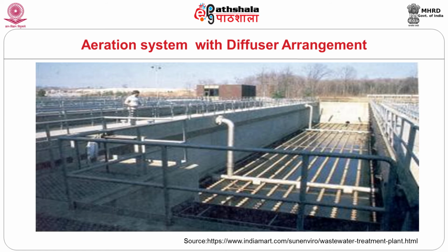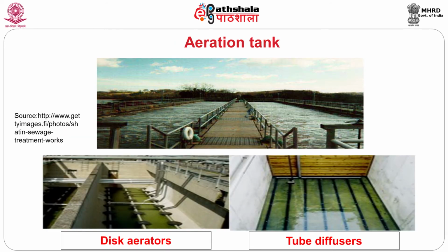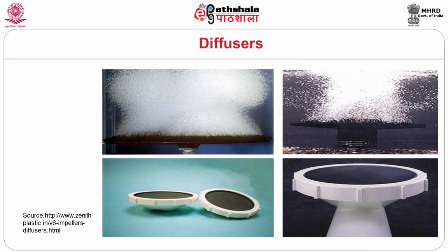So, we have to clean the diffuser plates quite often, otherwise a thin biological film will form around the surface of the porous media. So, this is the diffuser plates at the time of cleaning operation. This is the aeration mechanism. This is another arrangement we have. Nowadays, with the aid of this membrane type of diffuser plates, we can definitely enhance the oxygen transport rate when compared to diffuser plates.